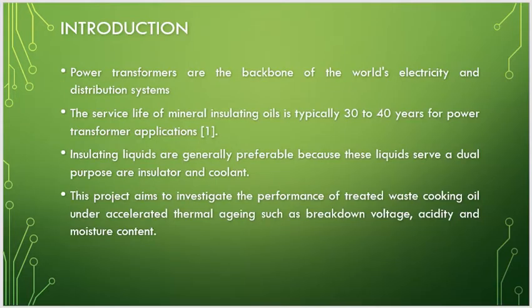For the introduction, power transformers are the backbone of the world's electricity and distribution system. The service life of mineral insulating oil is typically 30 to 40 years for power transformer application. Insulating liquids are generally preferable because they serve a dual purpose as insulator and coolant. This project aims to investigate the performance of treated waste cooking oil under accelerated thermal aging, such as breakdown voltage, acidity, and moisture content.